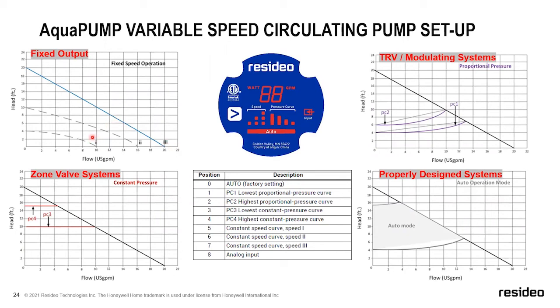Where I've seen this used is the oopsies. The example I just gave, where you've got one loop that's like 350 feet. Sometimes those variable speed pressure differential pumps just have a really hard time finding that one extraneous loop, and there's not a good fix unless you can cut it and bind it somewhere.